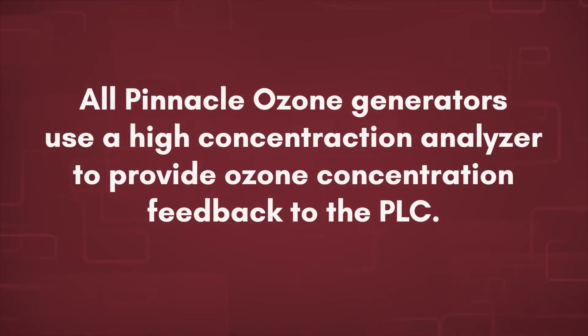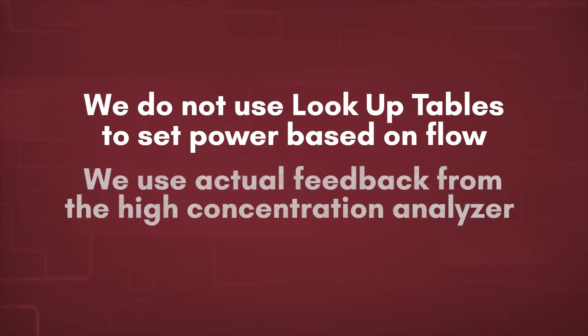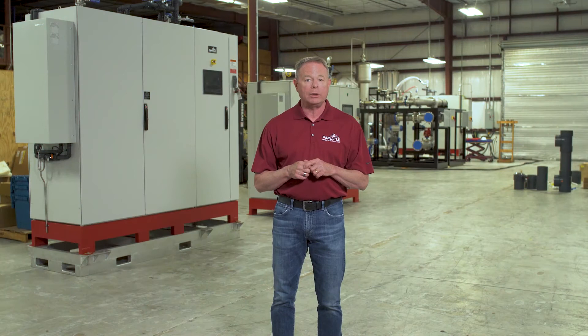All Pinnacle ozone generators use a high concentration analyzer to provide ozone concentration feedback to the PLC. Our control program adjusts the ozone generator power to hold the ozone concentration at a constant level as the flow is ramped up and down. We don't use lookup tables to set power based on flow. We use actual feedback from the high concentration analyzer to provide precise, accurate delivery of a constant concentration of ozone output.